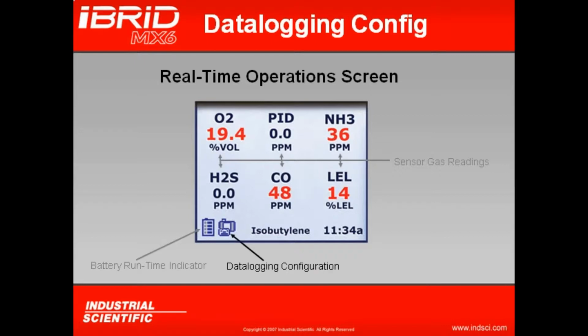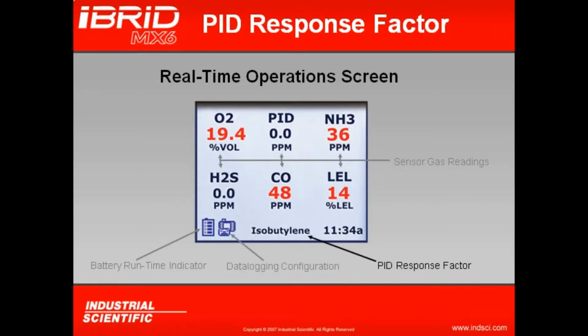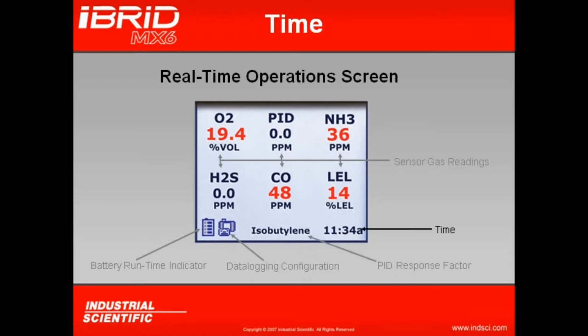You also have a data log configuration that may appear on a display letting you know how your data logger is currently configured. A PID response factor may also appear on your display as well. This is showing you how your PID is correlating its reading, and as we see in this example, the PID reading is going to correlate its reading in accordance with isobutylene. A time indication may also appear on the instrument to let you know the current time.